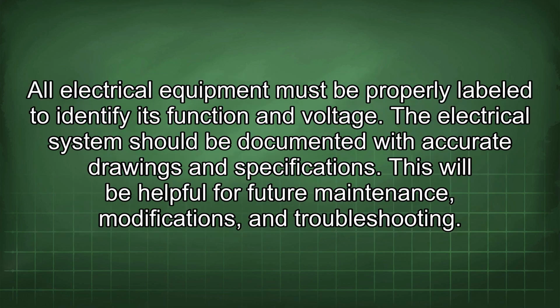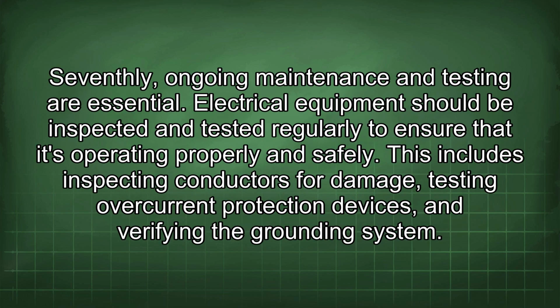All electrical equipment must be properly labeled to identify its function and voltage. The electrical system should be documented with accurate drawings and specifications. This will be helpful for future maintenance, modifications, and troubleshooting. Seventhly, ongoing maintenance and testing are essential. Electrical equipment should be inspected and tested regularly to ensure that it's operating properly and safely. This includes inspecting conductors for damage, testing overcurrent protection devices, and verifying the grounding system.